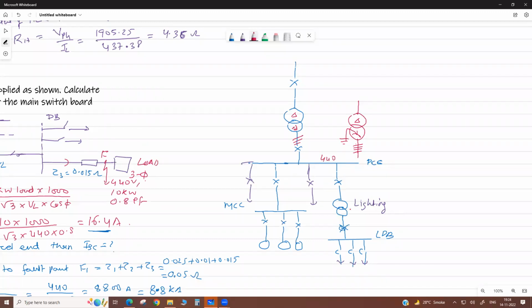Okay. Now with the lighting transformer we reduce this; the lighting transformer is 440 by 220 volt. So between any two phases we get 220 volt. So on board we feed the light with 2 phases, but it is 220 volt. Okay. Correct. So this is the purpose of the lighting transformer.